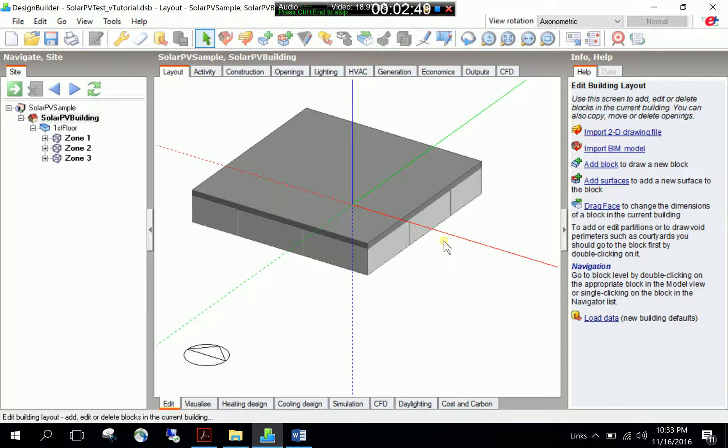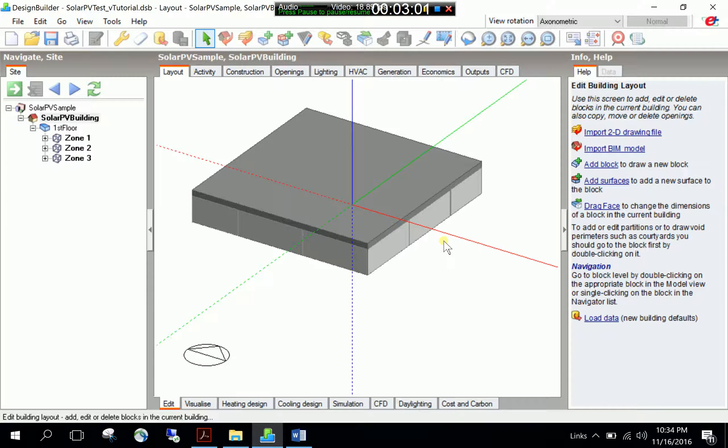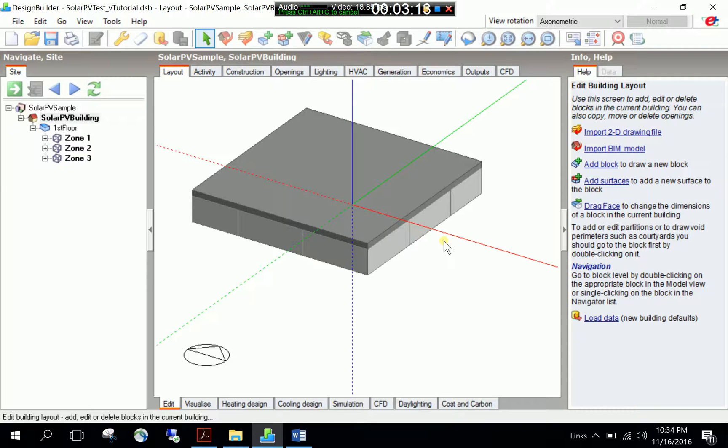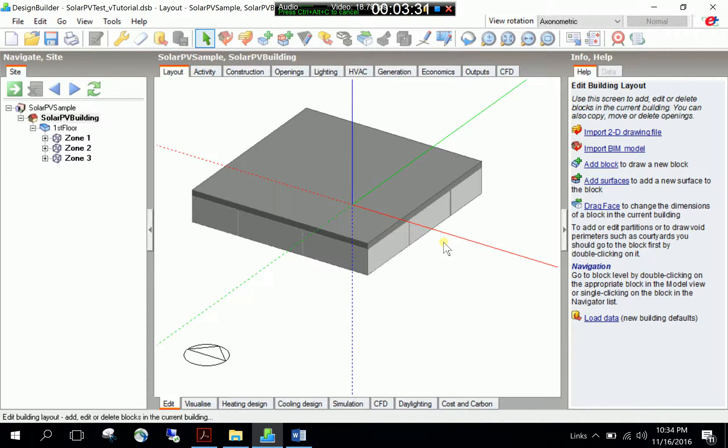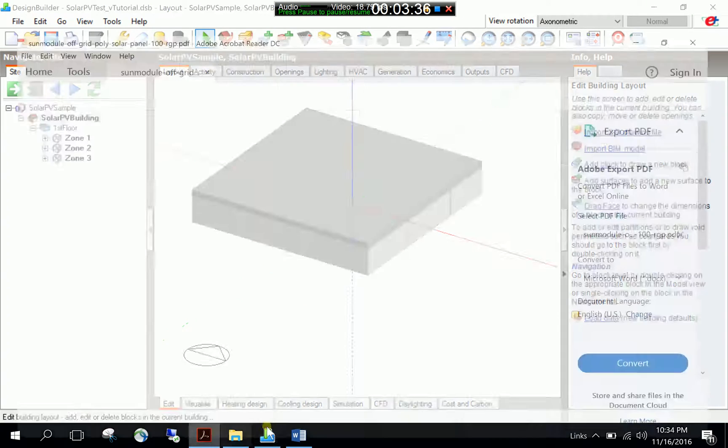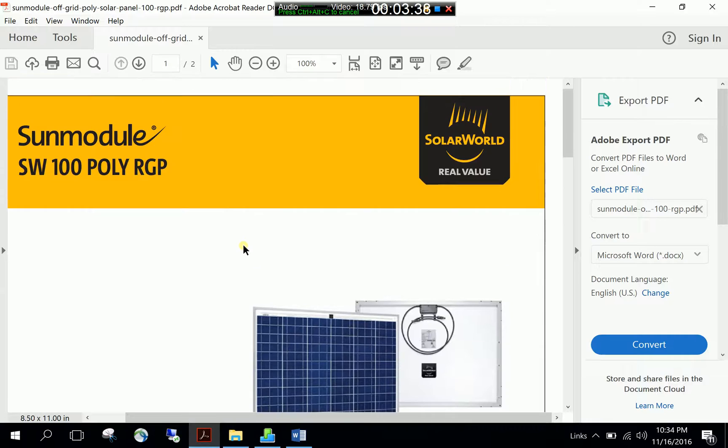It should be multiples of the active unit PV module area. For instance, if you have say one meter square of active PV unit module area, then the generated PV array geometry which is a collection of multiple PVs should be an integer multiple of this one meter square such as five. So if I have five PV modules of one meter square, I have five meters square entire area for the overall PV array. And this means that I have five unit PV modules connected in series to form the PV module drawn in the Design Builder interface. We are talking about active area. How do we get the active area? We get it from the manufacturer's specification.